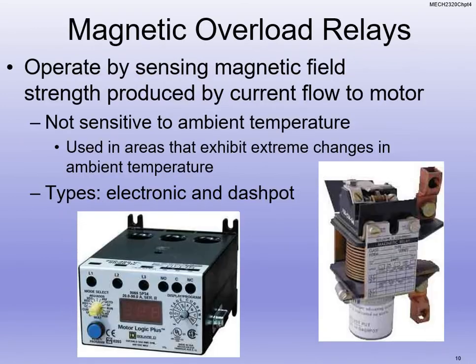So we have magnetic overload relays. They're not using temperature here. We are using the magnetic field given off by current. Remember in electrical class we talked about the left-hand rule. When you put your thumb in the direction of current and you curl your fingers in the direction of the magnetic field. Well, remember, as we have more current, our magnetic field is going to increase. So based on the magnetic field, we can detect how much current's going through there and trip based on that. Just the same way we use a clamp ammeter and things like that to read it.